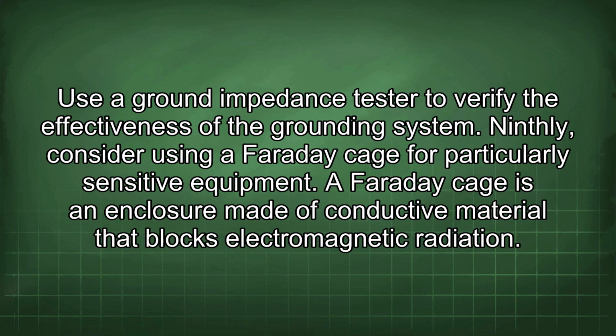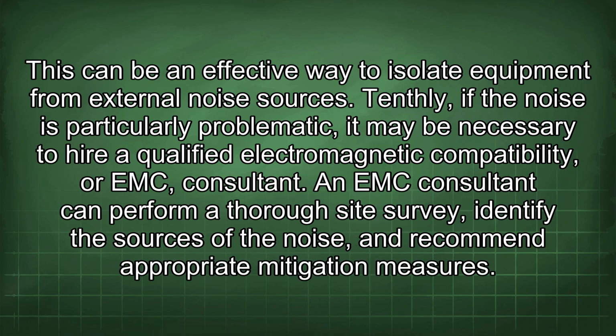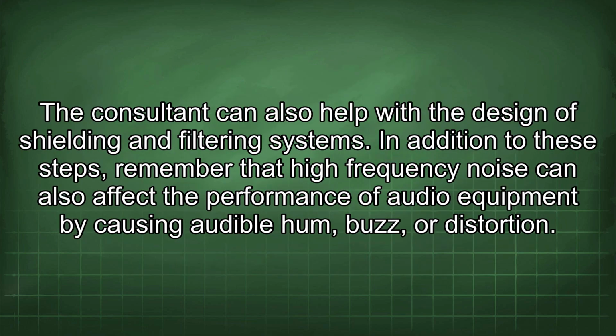Ninthly, consider using a Faraday cage for particularly sensitive equipment. A Faraday cage is an enclosure made of conductive material that blocks electromagnetic radiation. This can be an effective way to isolate equipment from external noise sources. Tenthly, if the noise is particularly problematic, it may be necessary to hire a qualified electromagnetic compatibility or EMC consultant. An EMC consultant can perform a thorough site survey, identify the sources of the noise, and recommend appropriate mitigation measures. The consultant can also help with the design of shielding and filtering systems.